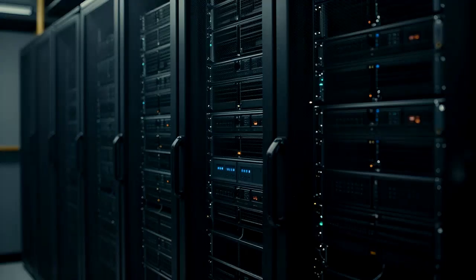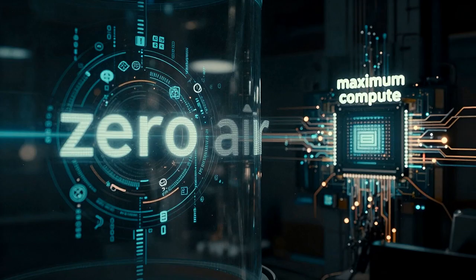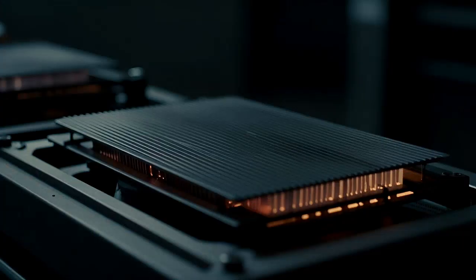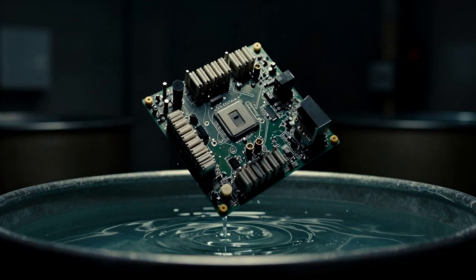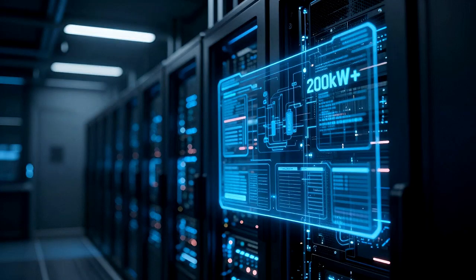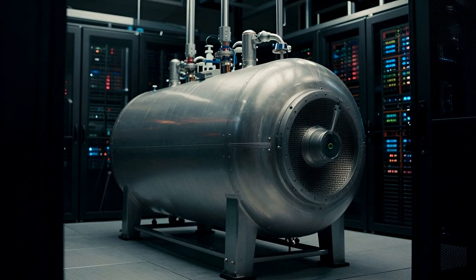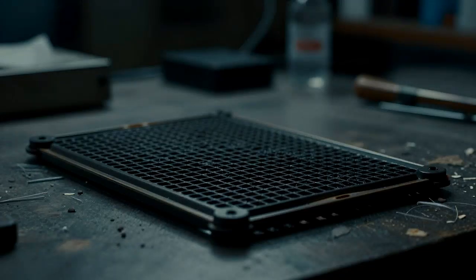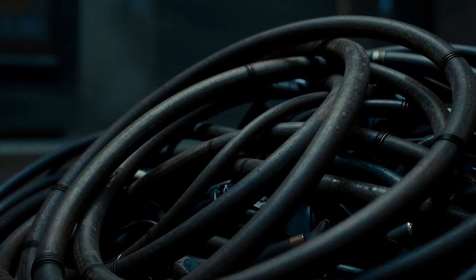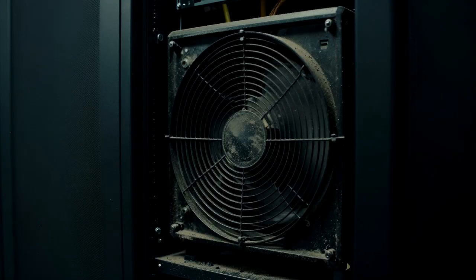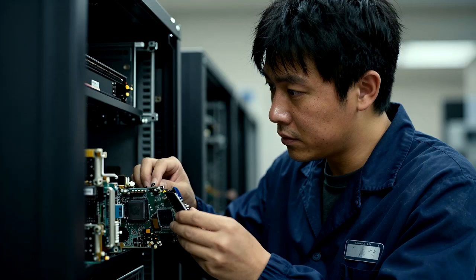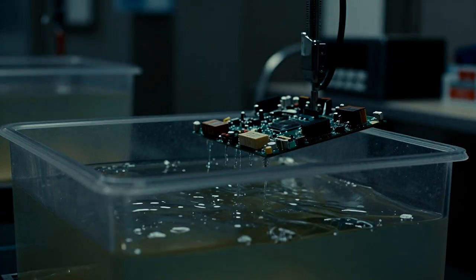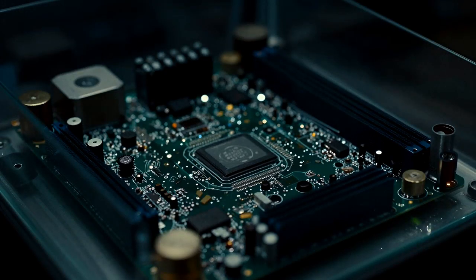For organizations seeking the ultimate, uncompromising solution to extreme density, where the goal is zero air and maximum compute, partial liquid cooling is not enough. They must submerge the entire machine. For the absolute vanguard of high-density computing, where rack power limits push relentlessly toward 200 kilowatts and beyond, the ultimate architectural solution is immersion cooling. This method discards the targeted cold plates, the intricate internal tubing, and the noisy server fans entirely. Instead, the server motherboard is removed from its standard rack chassis and plunged horizontally into a specialized heavy-duty tank that is completely filled with a thermally conductive liquid.